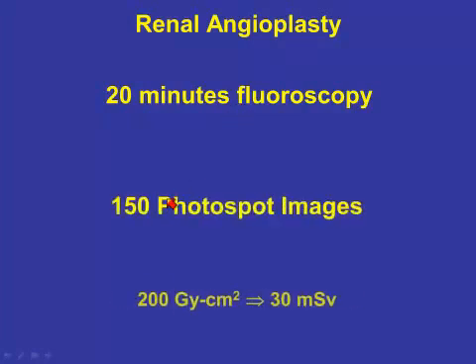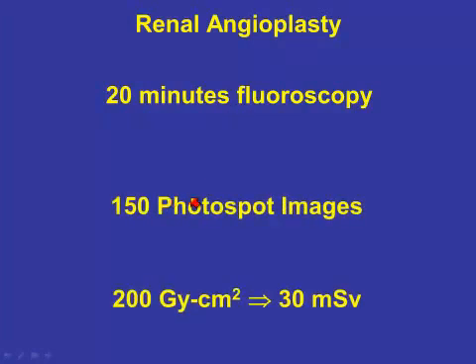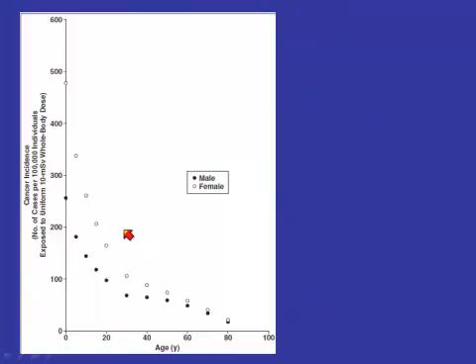If we take an IR procedure like renal angioplasty, you might use 20 minutes of fluoroscopy and generate 150 photo spot images. The Kerma area product — a median value I would expect to encounter in IR procedures — might be 200 gray centimeters squared, and that translates in an average-sized patient to an effective dose of 30 millisieverts.